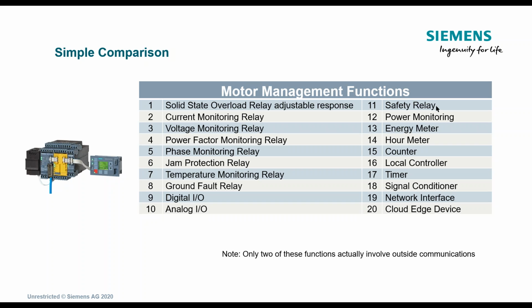Safety relay with SIMOCODE. I can do SIL 3, performance level E, within a motor control bucket, standalone or tied to a control system, an overall control system. Power monitoring, I can do kilowatt hours. I can do cosine phi, apparent power. Energy meter, I can do an hour meter.